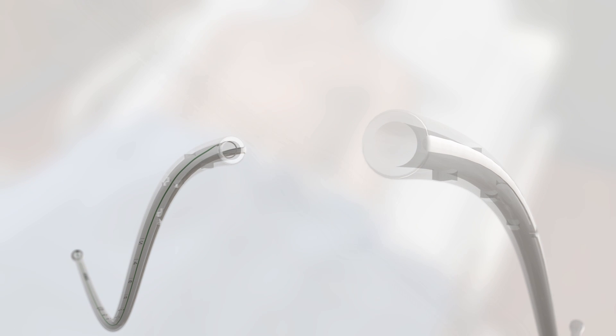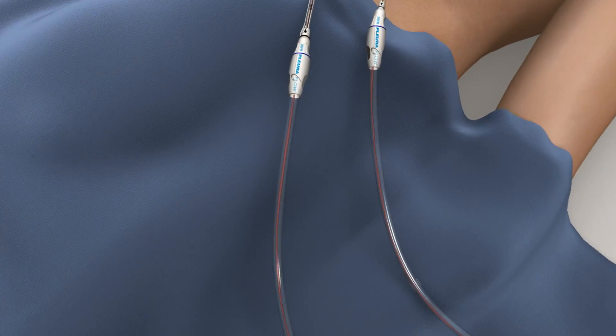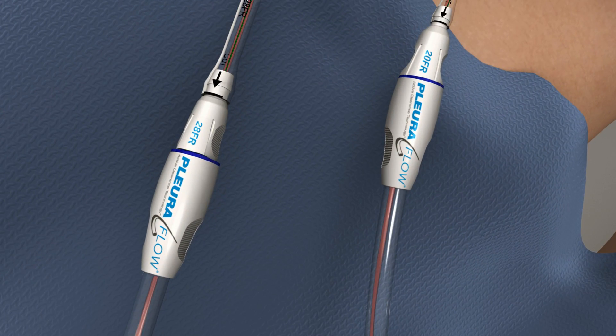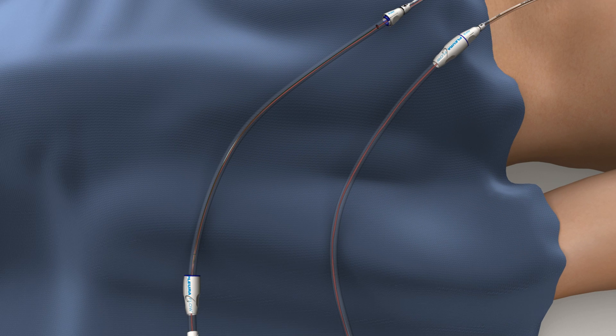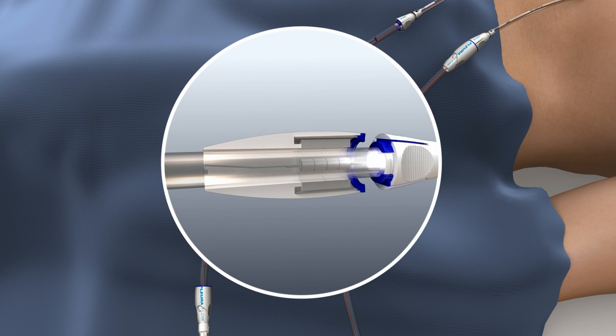Smaller caliber PleuraFlow systems can provide superior drainage by ensuring chest tube patency is maintained. The system is actuated by releasing and sliding the shuttle guide toward the drainage canister. The shuttle is magnetically coupled to an internal clearance loop to maintain the internal sterile environment.